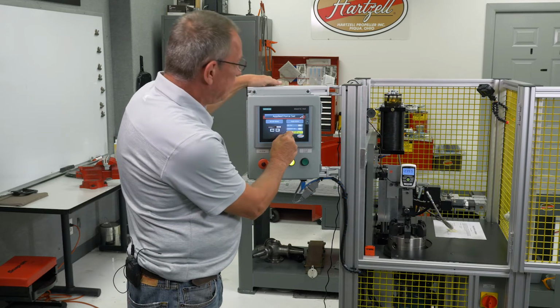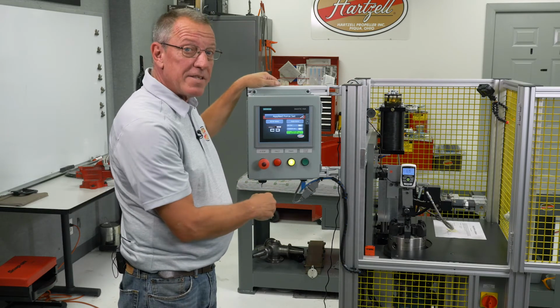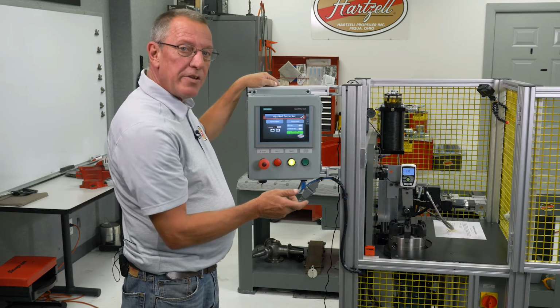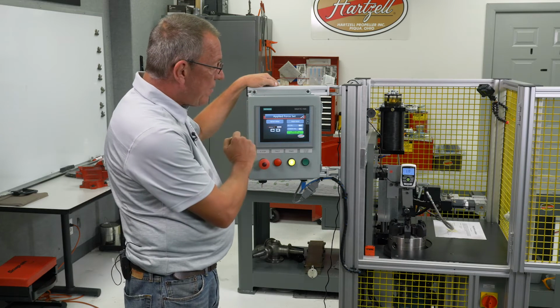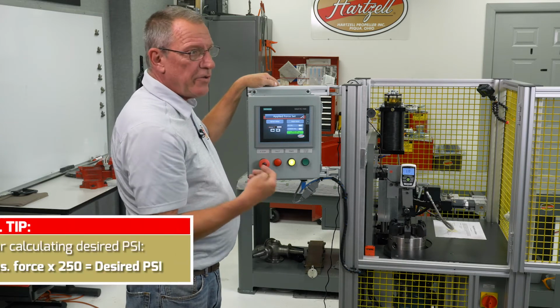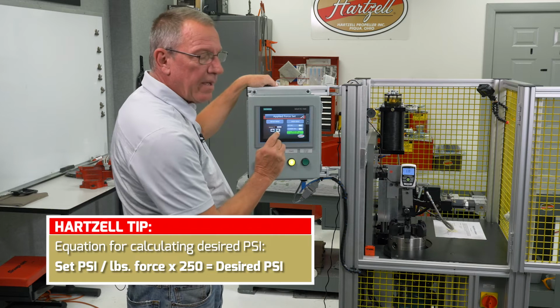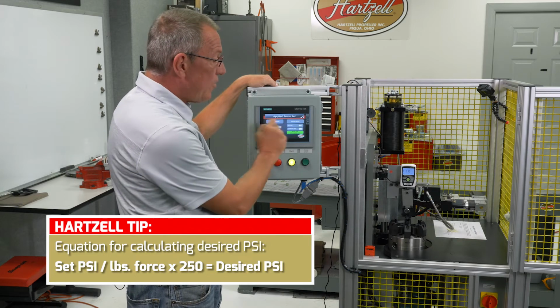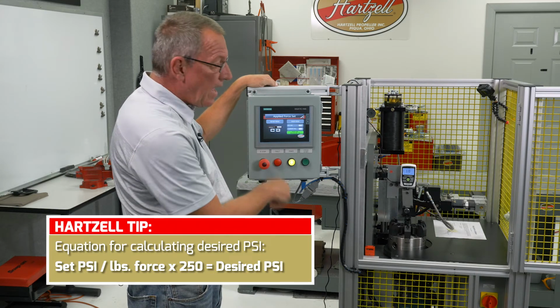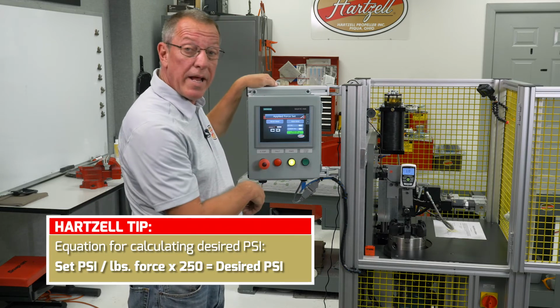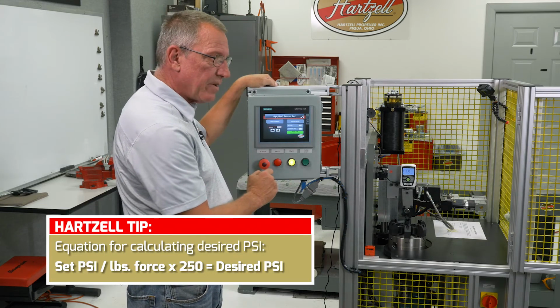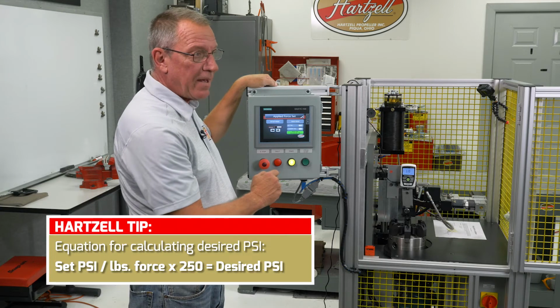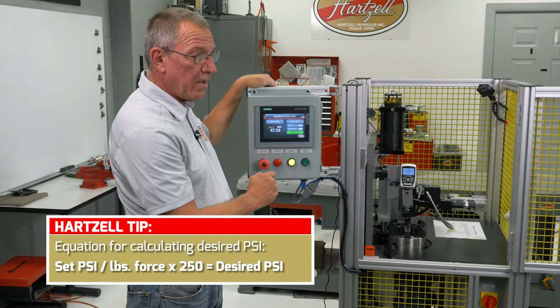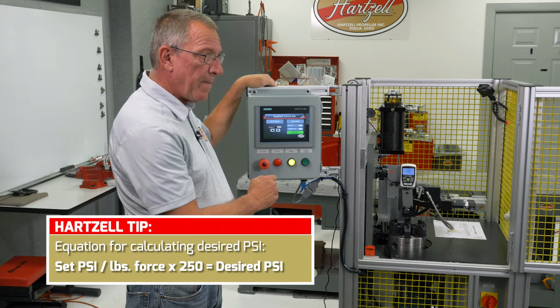And I'm showing 240. My target setting is 250 plus or minus 2. So what I'll need to do here, I'll have to reset my set PSI. To do that, I take my set PSI, which is 1750, and I divide that by 240, which was the number I got on my gauge, and then multiply that times 250.